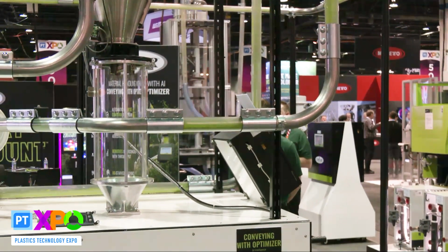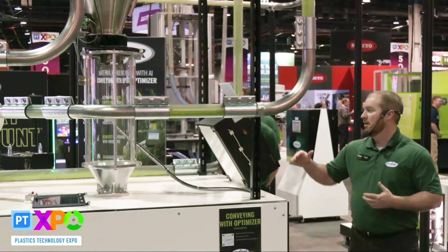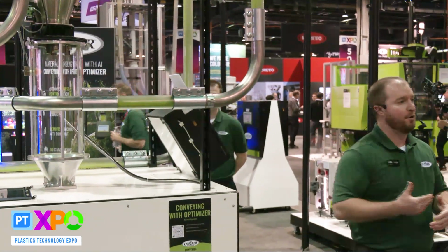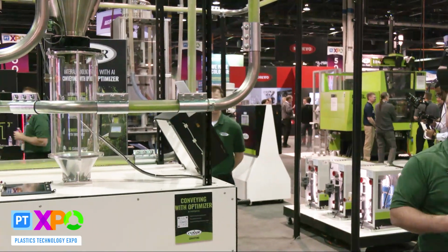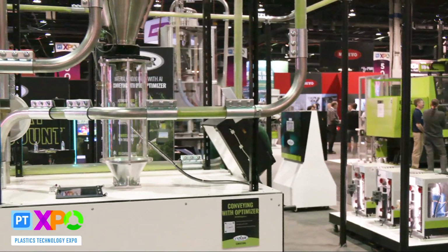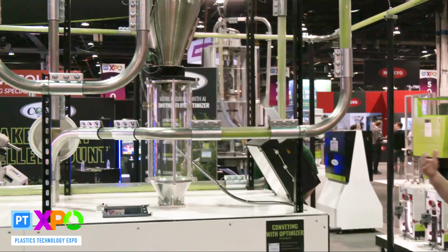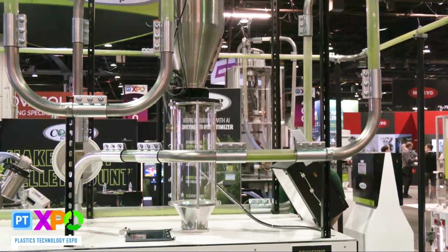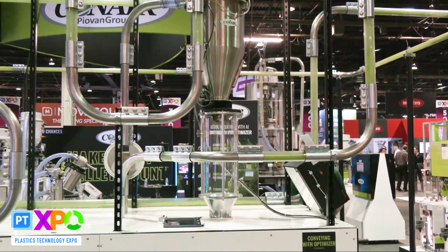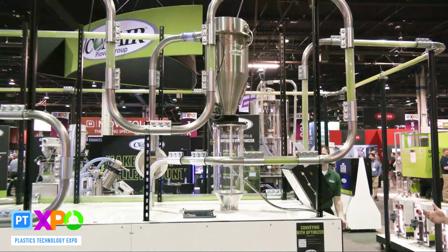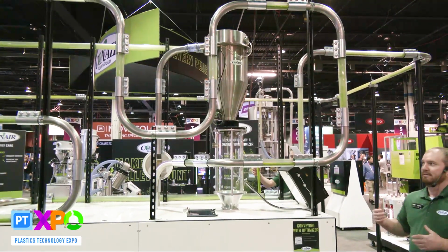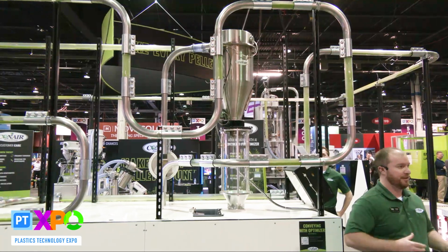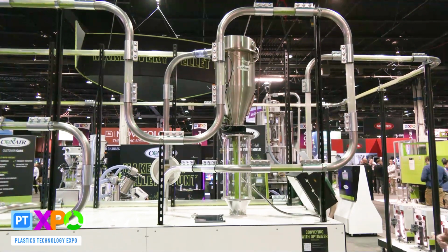So as I've been talking, our valve has adjusted and we're back up over 8 inches of mercury. Within about 2 to 3 load cycles, we've already caught back up to the vacuum pressure that we were at when we started. So now we can take that leak away, and all that air that we were inducing with the leak is going to go away.